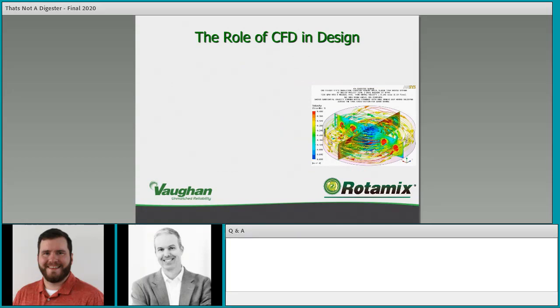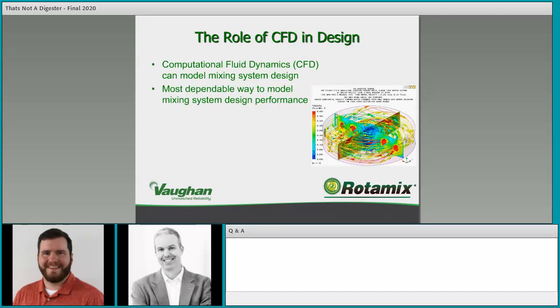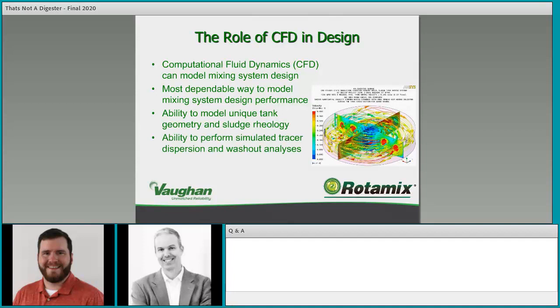Let's talk about the role of CFD in design. Computational fluid dynamics can model the mixing system design — it's the most dependable way to model mixing system performance. We have the ability to model unique tank geometry and sludge rheology, and the ability to perform simulated tracer dispersion and washout analyses. For a blend tank, tracer dispersion will tell you how quickly something added from some process will be blended into the sludge. It provides in-depth analysis into what the performance of the system will be before it's even built.